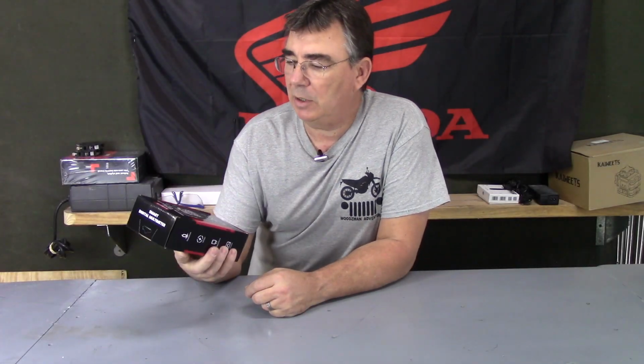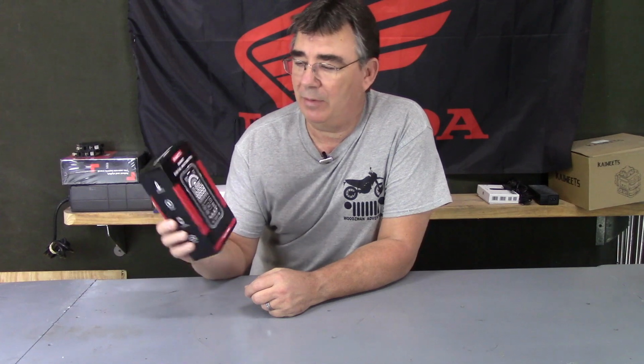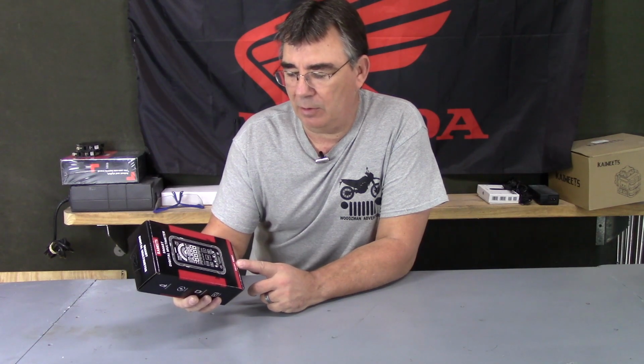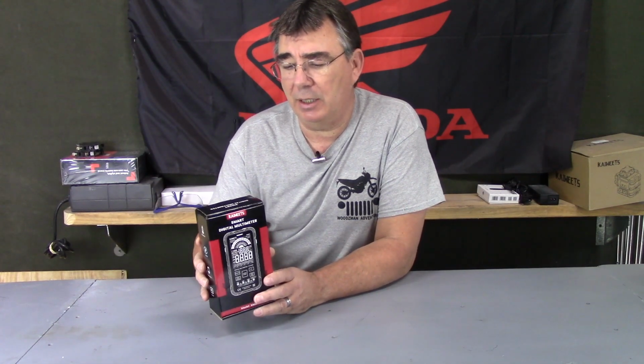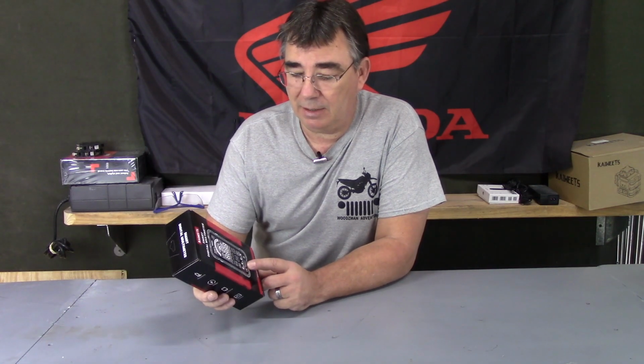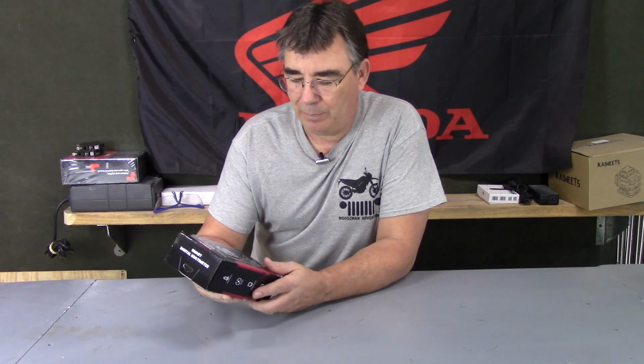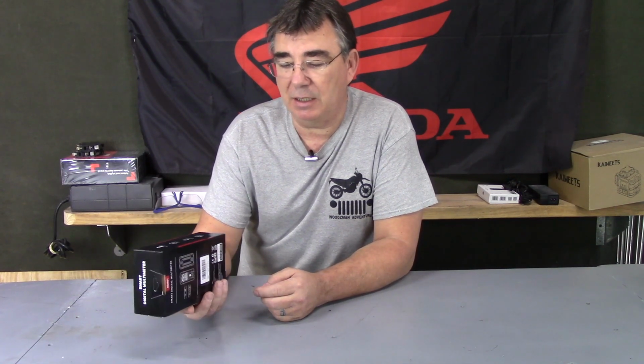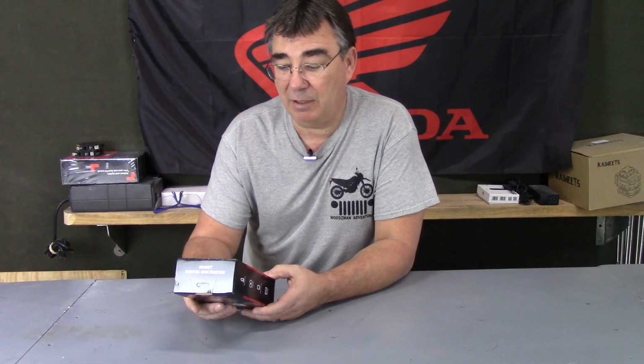So I have another multimeter here to test, this one from KAIWEETS, I believe that's how you pronounce it. I've tested a few different ones, not from this company, but this one is the model KM601, a smart digital multimeter. It says it's 10,000 counts, but it's actually 9,999 — the meter face shows 9,999 counts, but the box says 10,000. Anyway, let's take this thing out of the box and check it out. This should be a good multimeter for testing resistance, capacitance, voltage, and current. For the price, instead of buying the expensive brands — I do have an expensive brand, but it actually works no better for what I do.